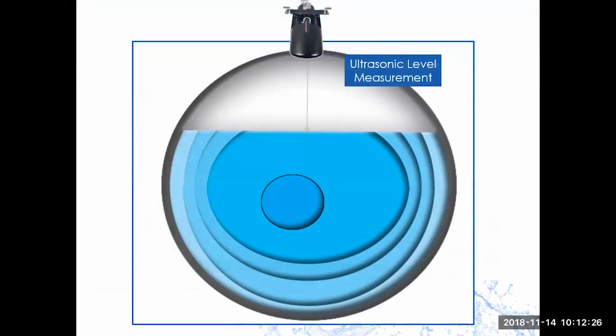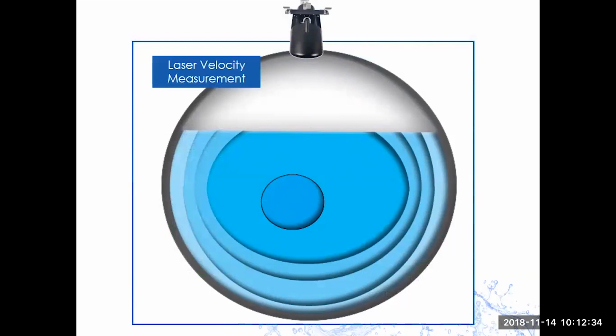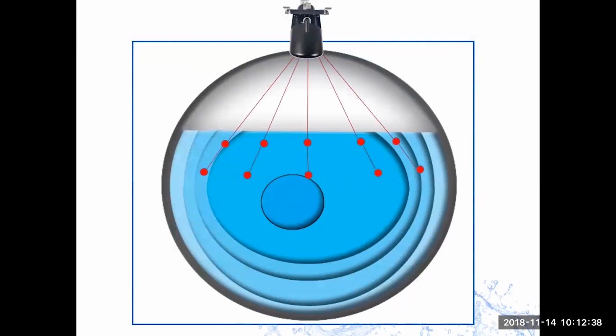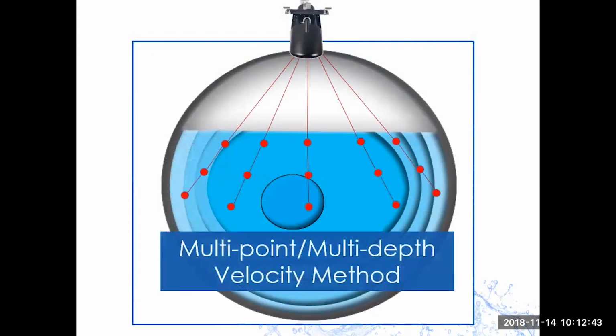So how do we run this thing? Well, we can set it up a couple different ways. One way, we do an ultrasonic level measurement. We know where the water is. We can do single point, multiple points, or any combination of those. So in this case, we're doing a full 15-point spread, which is known as a multi-point, multi-depth velocity method. When you look at these, each one of these readings in this diagram represents 5,000 velocity readings. So when you do this, if you get all 15, you're getting about 75,000 velocity readings in roughly a minute and a half.